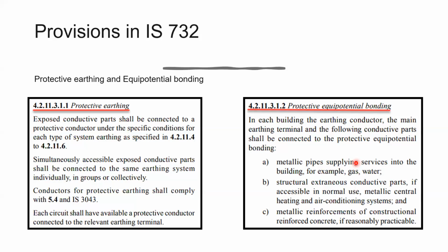The second point is about the protective equipotential bonding, where in each building, the earthing conductor should be connected to the main earthing terminal, that is the MET, and the conductive parts should be connected to the metallic pipes, as it was shown by Mr. Gopal Kumar earlier, which are supplying the gas or the water, the structural conductive parts, metallic central heating and air conditioning systems, and the structural reinforcements of the RCC of the building, to make it the protective equipotential bonding.